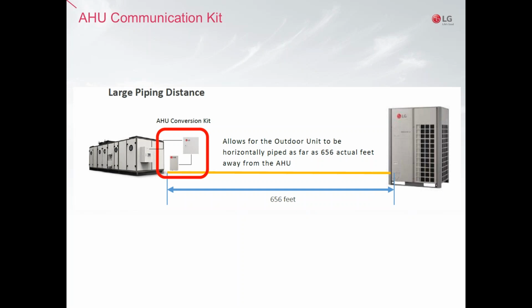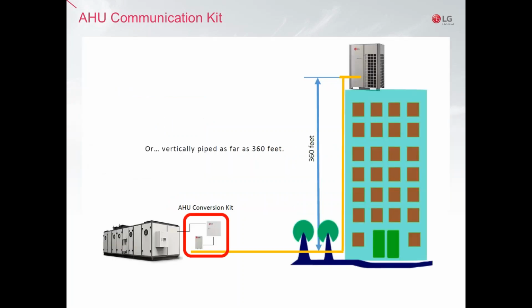But not only horizontal distance is important. We also have a vertical distance of up to 360 feet between the air handling unit and the condenser unit, which is very helpful when you want to retrofit chilled water systems to VRF and put all the condensing units on the roof, for example. The only point to note is that the EV kits and their air temperature controller must be contiguous to the air handling unit for proper operation.